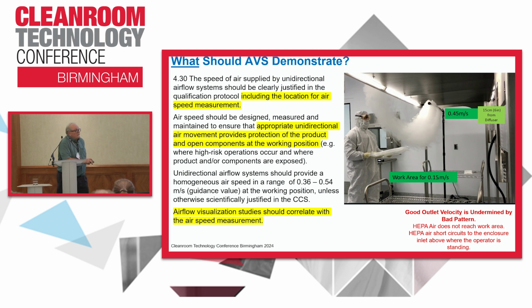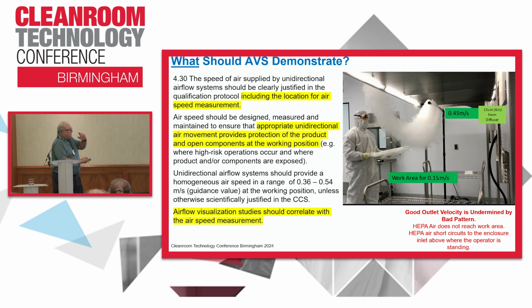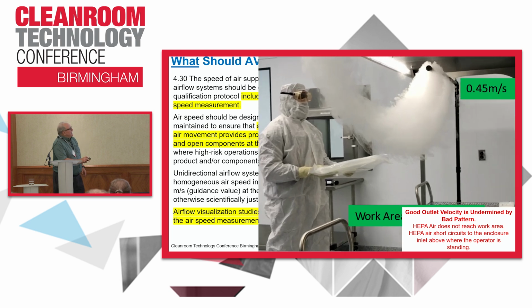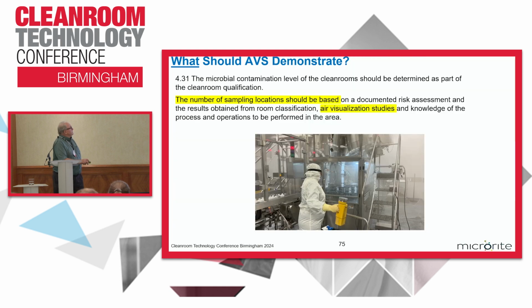We are opening up clean systems. It was validated. They were making product. Everything was good until they did the smoke study. And the first smoke study they did, it showed it was wonderful because they used a heavier than air water fogger, and it showed they had perfectly fine airflow. We'll talk a little bit more, but you can see the real issue, right? We weren't getting first air to where the products were being handled.